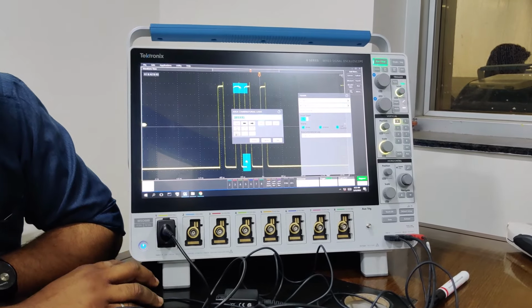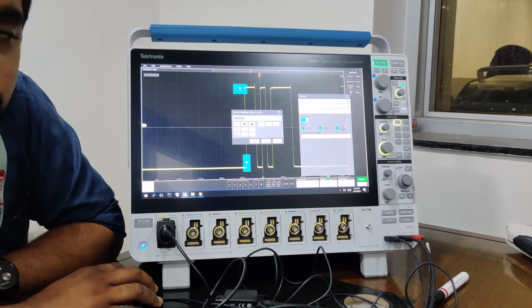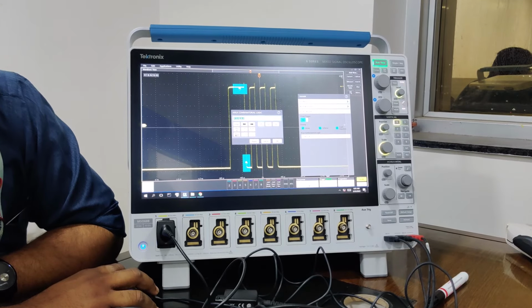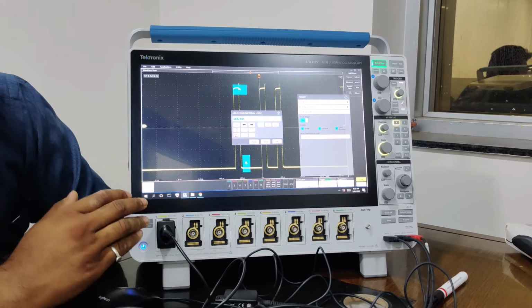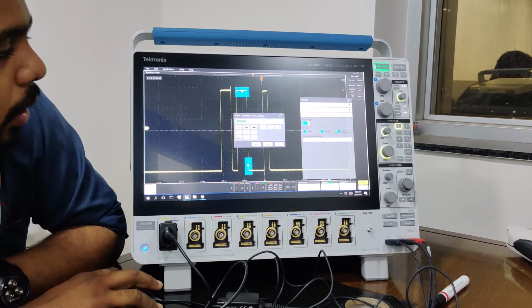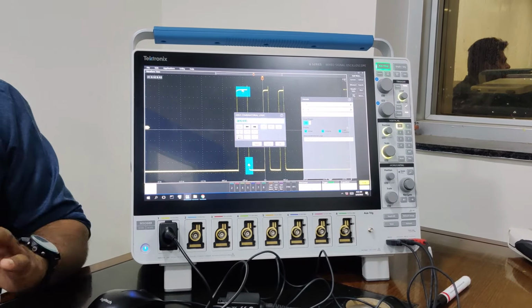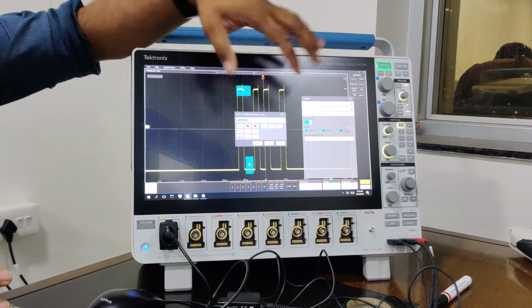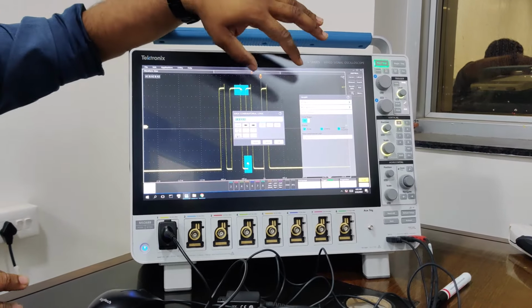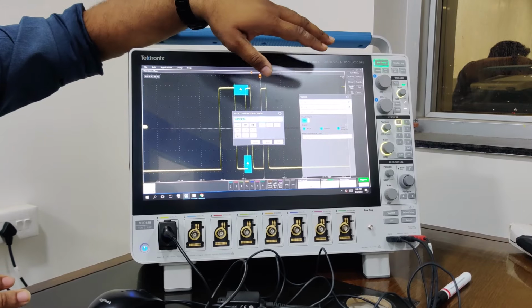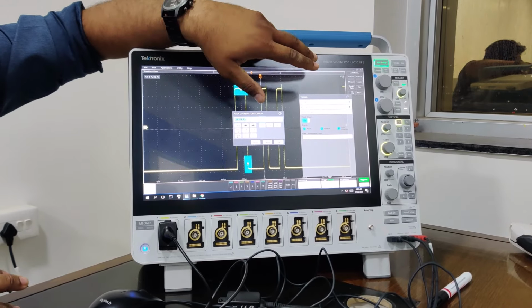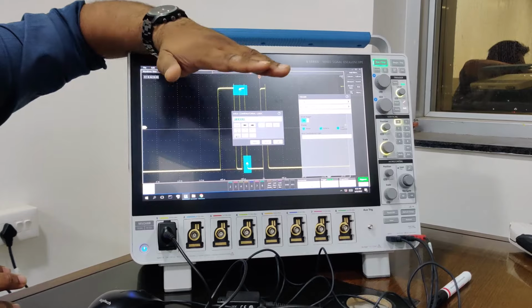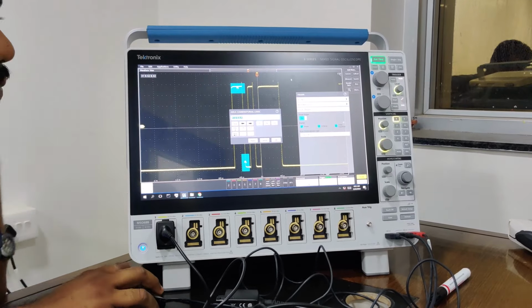What I want: A and B, or A1 and A2 and A3, or A1 or A2 or A3, or whatever criteria. You can set your own logic. If you want all three triggers, you can set the condition accordingly. If you want any one of them, you can set that condition. A or B, A XOR B, those things are already present.